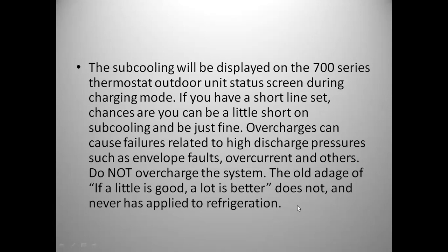So as a rule of thumb, which we'll get into here in just a minute, as far as charging the Rheems, you always want to undershoot what the required subcooling is, and that will give you some fudge factor to accommodate for real world issues.